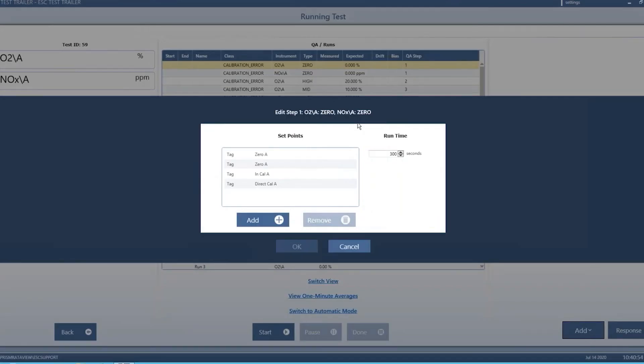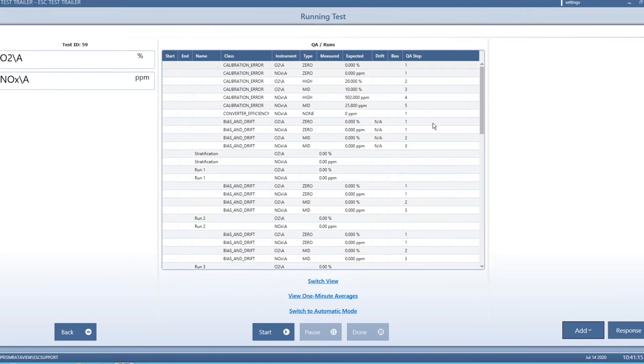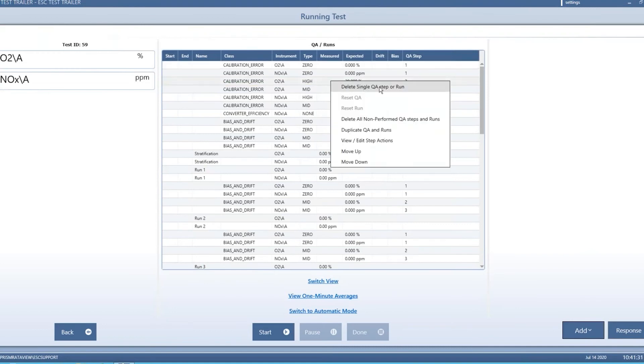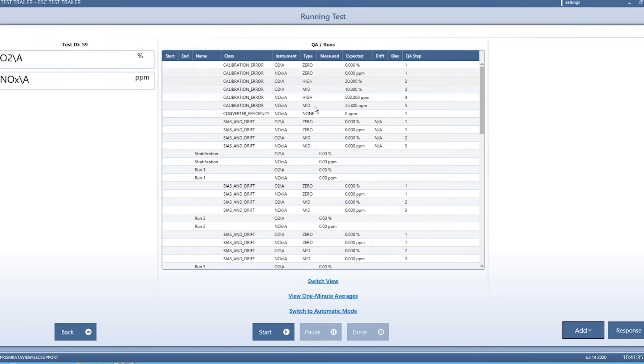For example, in one step we're turning the zero A on in Cal A and the direct Cal A bits on for 300 seconds. You can even edit the step actions — take steps out, add different bits to the step, adjust the time. You can delete them and move them up and down. We tried to provide that flexibility to prevent you from getting partway through a test and being forced into something that wasn't what needed to be done.